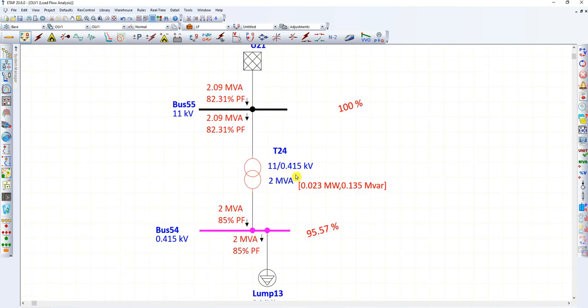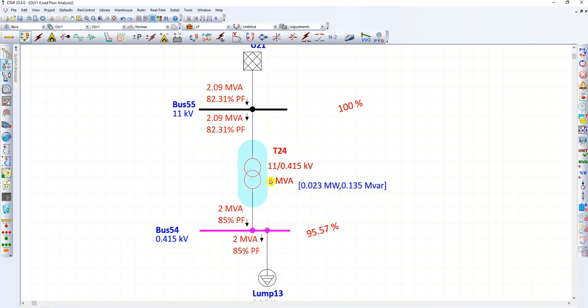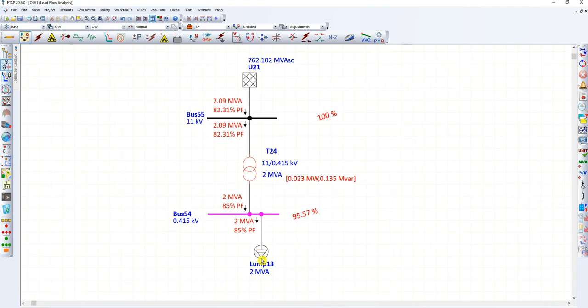The loss within the transformer is 23 kW real power and 135 kVAr reactive power. This real and reactive power loss within the transformer needs to be compensated. That's why the 2 MVA transformer is drawing 2.09 MVA from the source side — because it needs to feed the downstream 2 MVA load.